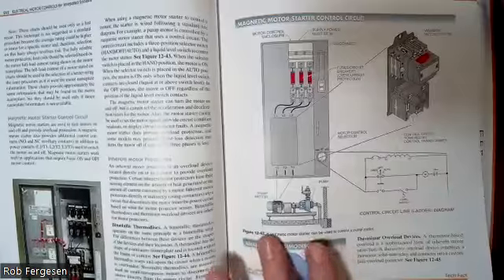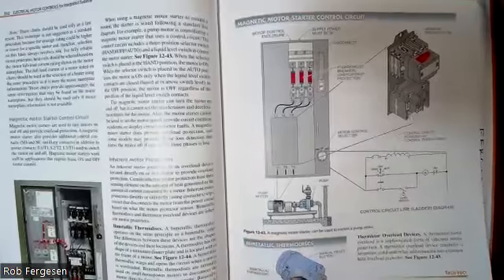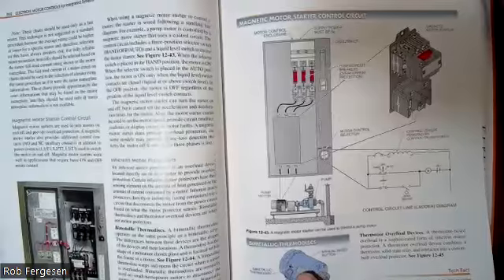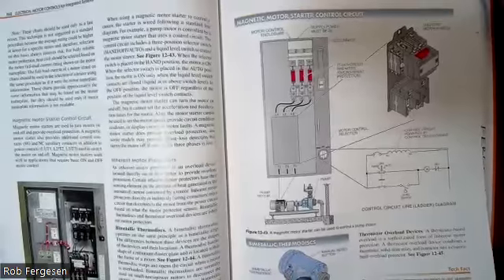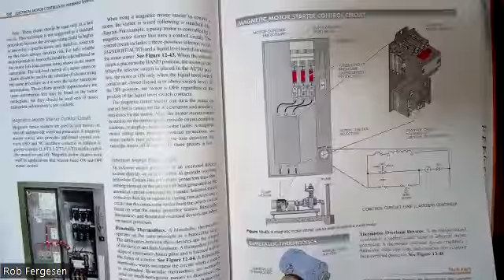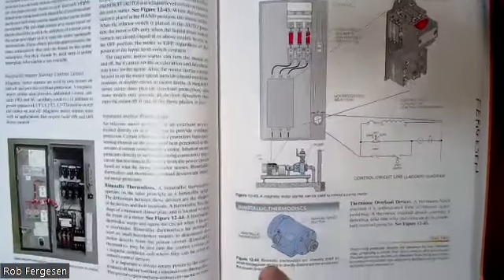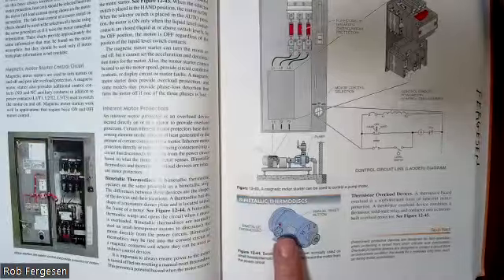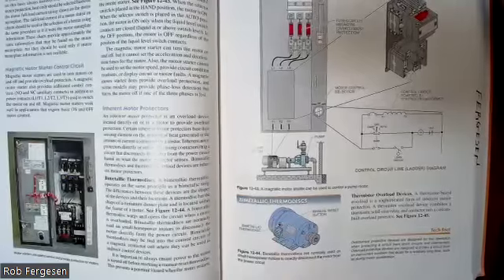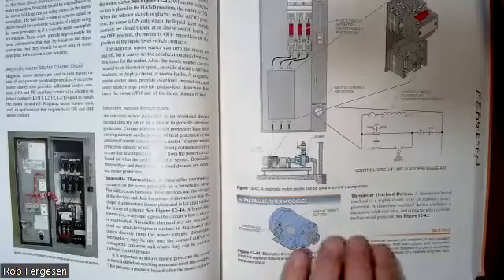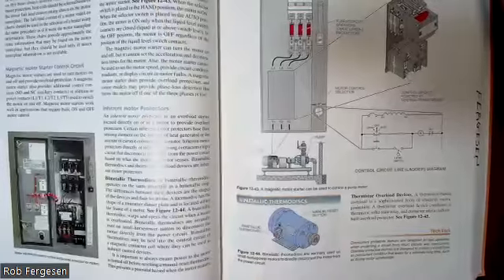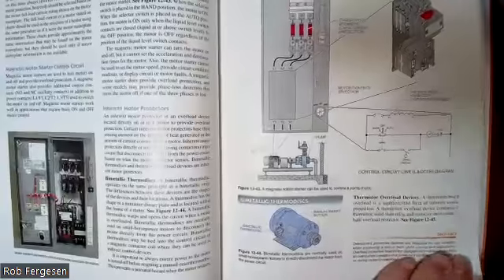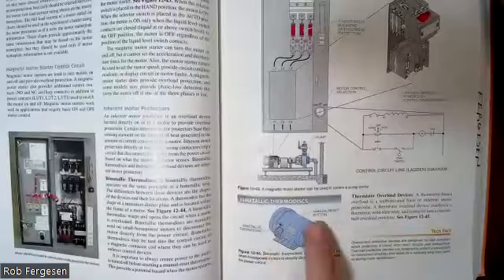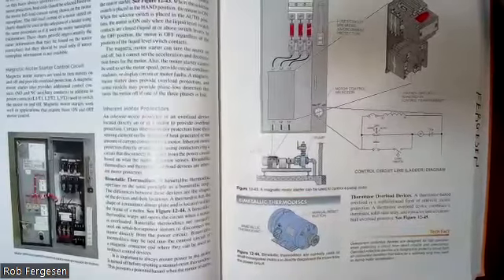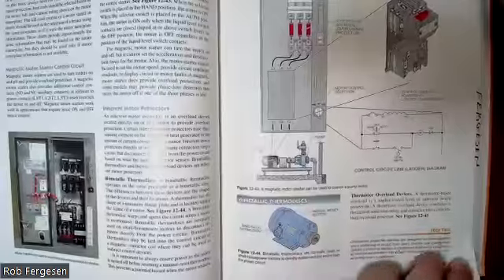There's a lot of different other kinds of motor protection, like in old school AC motors, especially single phase, you have overheat bimetallic thermal discs attached right to the motor. So if you run that motor too hard and too long, that little bimetallic thermal disc will pop. The motor will need to be cooled, and then you can reset that by pressing it back in again. They are a pain. They tend to be older motors. And if you get one of these that blows on a regular basis, there's a problem with the coils in there. Chances are you need a new motor.